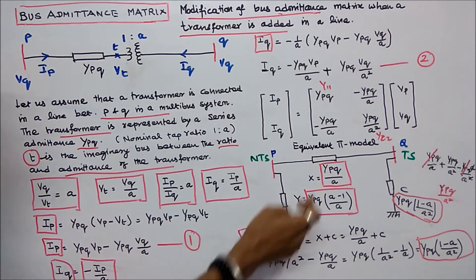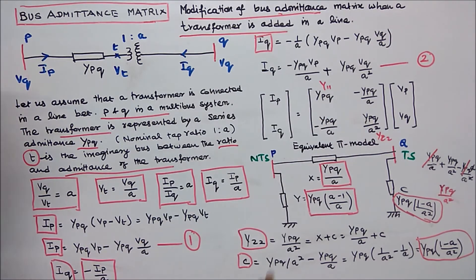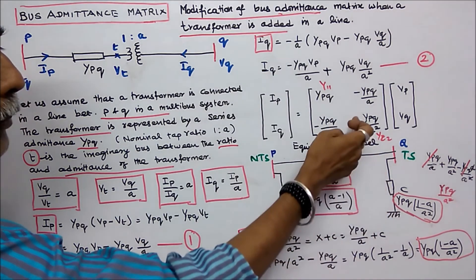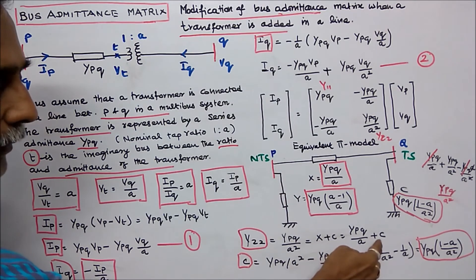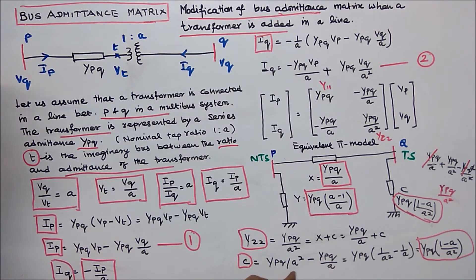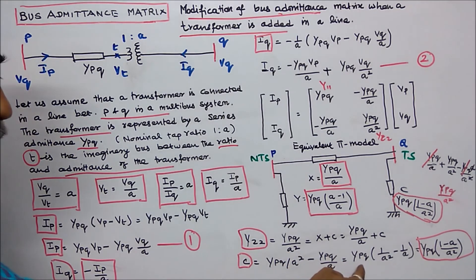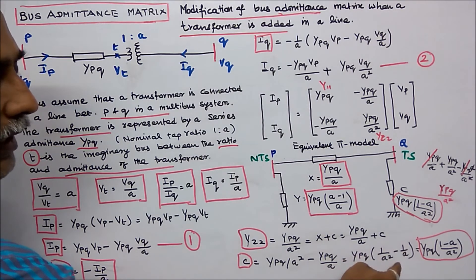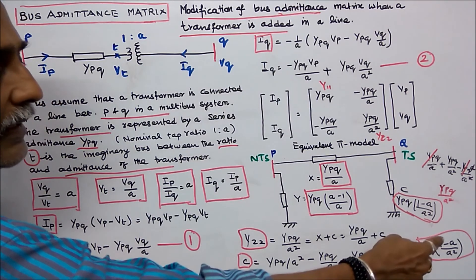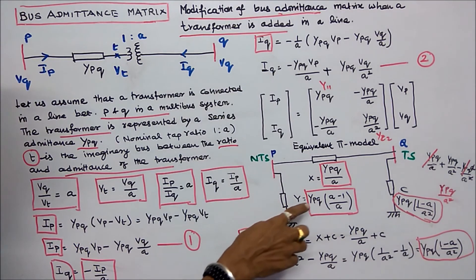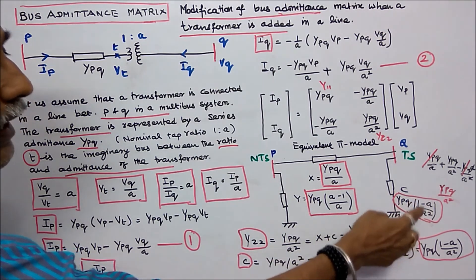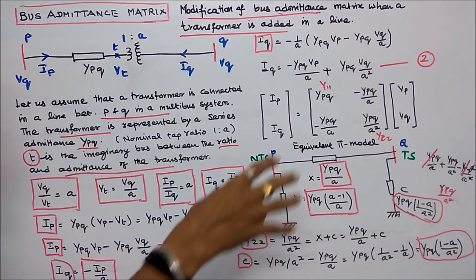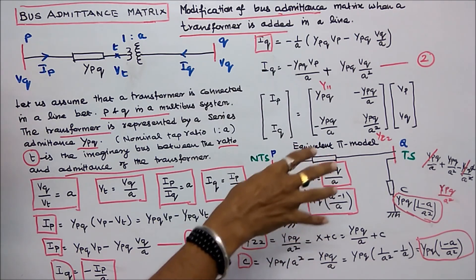Y22 is equal to YPQ divided by A squared. So X plus C equals YPQ divided by A squared, and X equals YPQ divided by A. Therefore C equals YPQ divided by A squared minus YPQ divided by A, which equals YPQ multiplied by (1 divided by A squared minus 1 divided by A). This can be written as YPQ multiplied by (1 minus A) divided by A squared. On the tap side, the shunt admittance is YPQ multiplied by (1 minus A) divided by A squared, and the series admittance is YPQ divided by A.